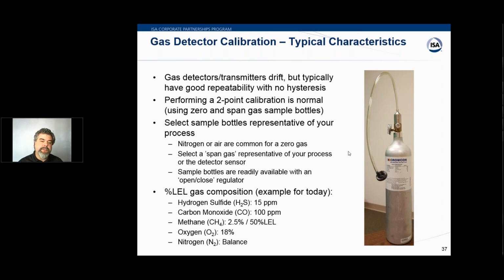With gas detectors, they do drift, but pretty much they do have good repeatability and no hysteresis, so there's no reason to go up and back down again. That's the whole reason for going up and down, is testing for hysteresis. So performing a 2-point calibration is good, dealing with 0 and then some level of span. If you are doing an oxygen sensor, you just need to be aware of that earlier poll question we asked of what percentage of oxygen is in the atmosphere normally, and it's around 21%.